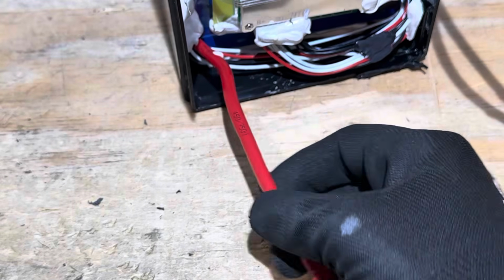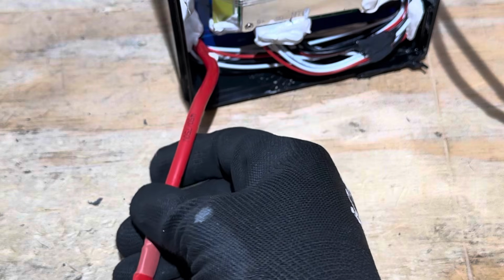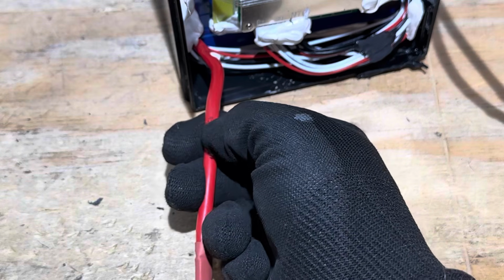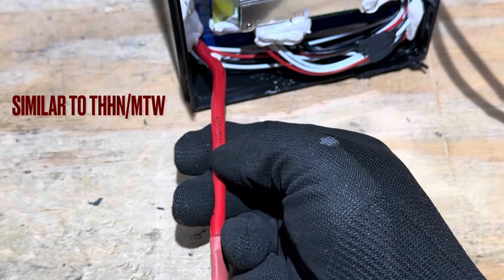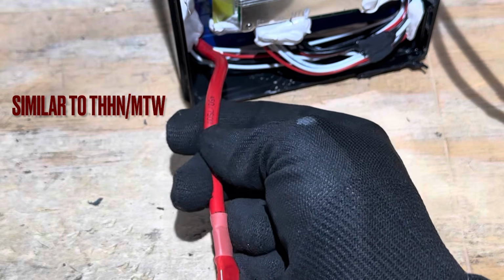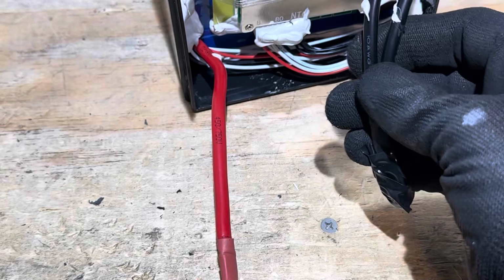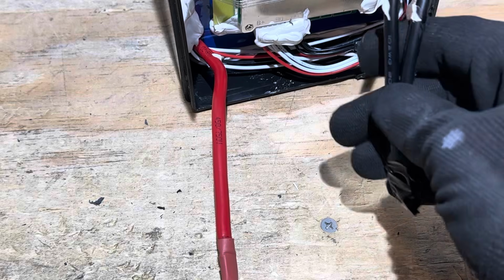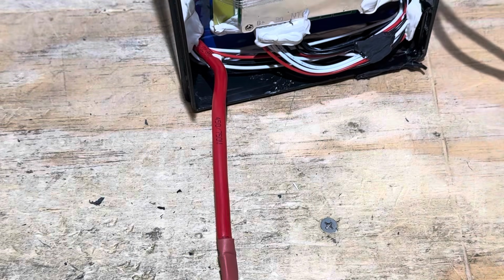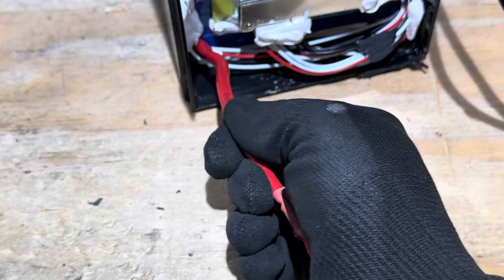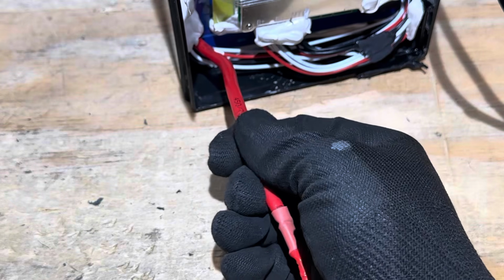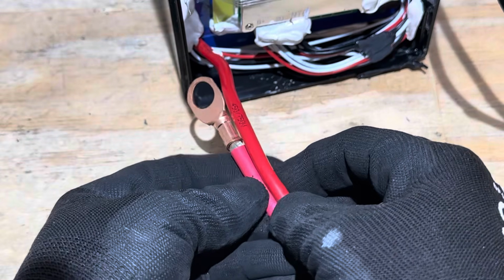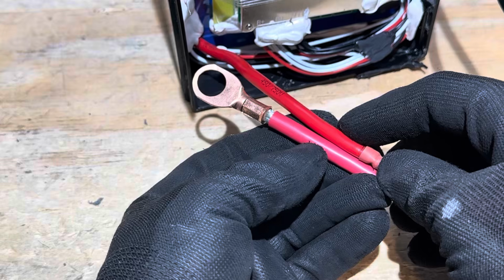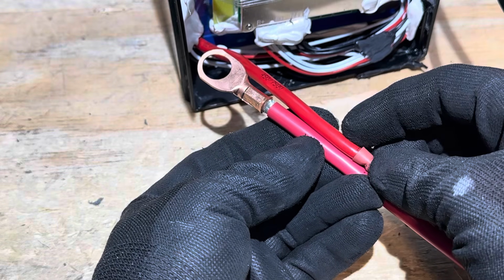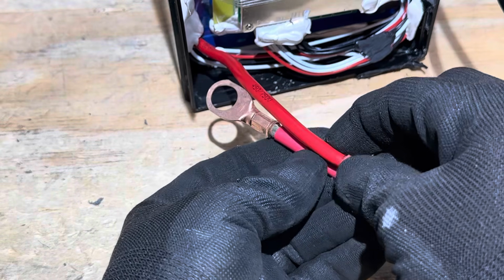Still can't find any info on this positive lead, but I will tell you with 100% certainty that that is not a silicone jacketed cable. That is a high heat nylon or high heat thermoplastic jacket, whereas the negative leads are silicone jacketed lead. So, silicone jacket is rated at a higher temperature than whatever this is. But that appears to be an 8. Here's a 6 gauge wire right there for comparison. As you can see, the 6 gauge wire is quite a bit larger than this one that's in this battery.